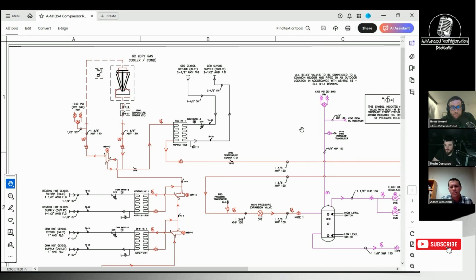No, I think it depends on the orientation. Typically, if you go to the flash tank, that's good enough, right? Because you're getting the majority of all the liquid and everything out of there. Mm-hmm. If it's a larger industrial system, we're pulling it out slow. We can dump it into the low side of the system, in front of a large accumulator. So a little bit of liquid's not going to affect anything or hurt anything.